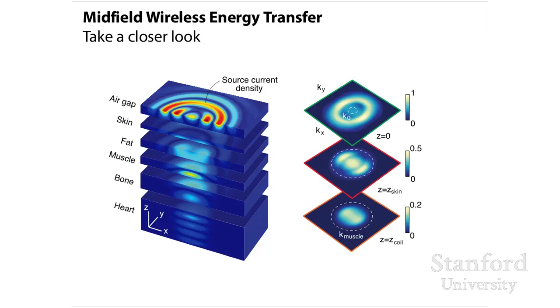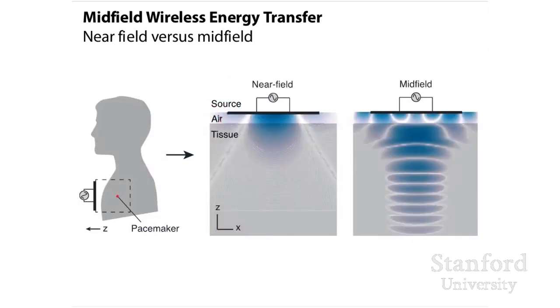Now, this is very different from inductive coupling, where the magnetic field outside the source is non-propagating. When it interacts with the tissue, it is also non-propagating. And that's the reason why, with the inductive coupling method or the near-field method, the magnetic field has limited penetration, because it's non-propagating outside and it's also non-propagating inside. While the optimal source is non-propagating outside, but it becomes propagating inside the tissue when it interacts with the tissue. And this is the fundamental difference between the optimal solution versus the one that we conventionally use. And because of this property, we are able to make the devices very small and implant them pretty deep inside the body.